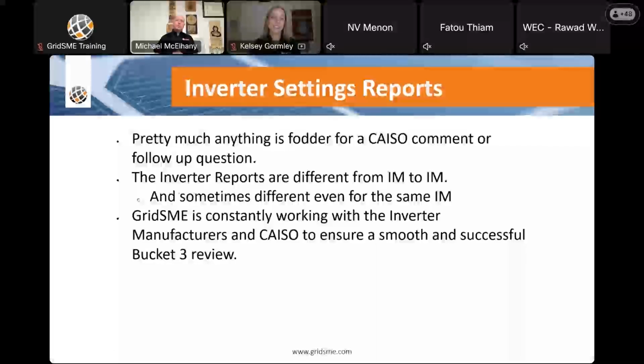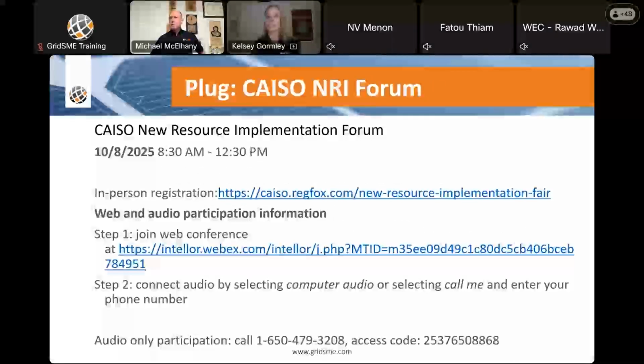And again, inverter reports are different from inverter manufacturer to inverter manufacturer. And even within the inverter manufacturer, depending on who the engineer is, I've got several different inverter manufacturers where I get different looking inverter reports depending on who's the project engineer for the inverter. GridSME is constantly working with the inverter manufacturers and CAISO to help ensure a smooth and successful bucket 3 review.